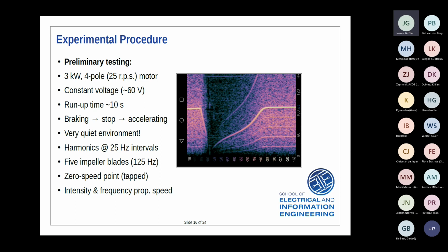I'll try and emulate the sound of this machine. So the machine is running full speed backwards, first of all, so running at full speed. We try it again. Then what we do, we disconnect the phases, we reverse 2 phases, re-energize. So the machine coasts for a moment whilst we're fiddling around with cables, so it's slowing down. And then when we re-energize it, it goes into a braking region, and you can see it decelerates very quickly. So here it's coasting, and here it's decelerating very quickly to standstill, basically. I'll do the sound again. And then it accelerates in the other direction. Okay.